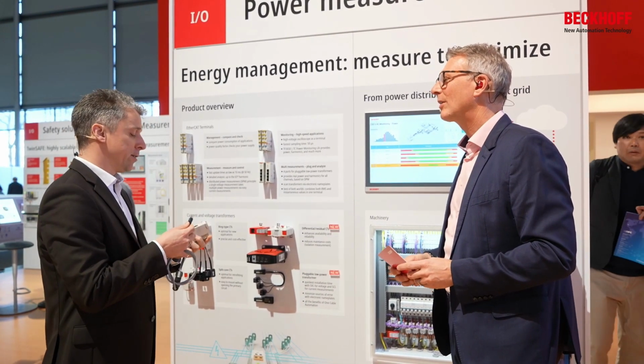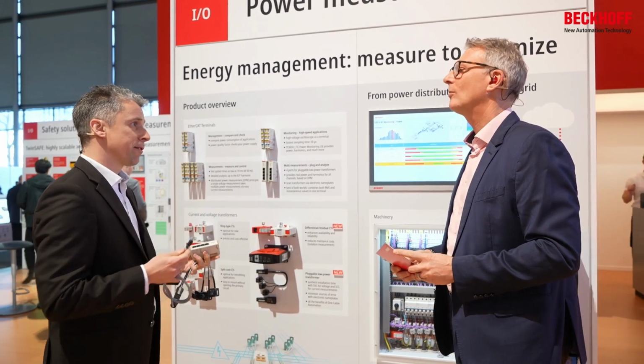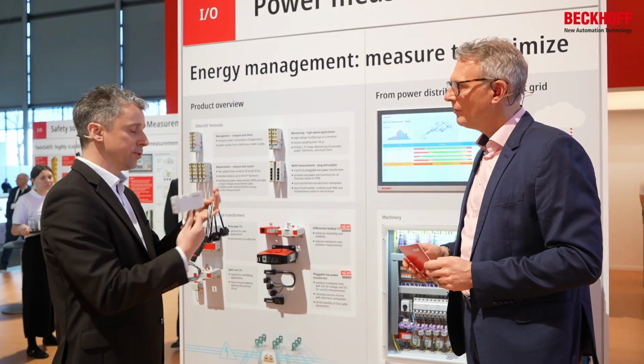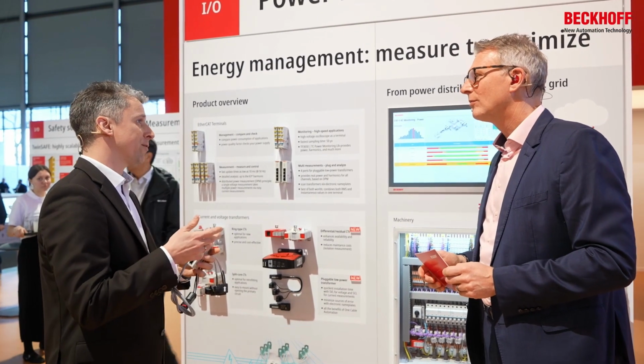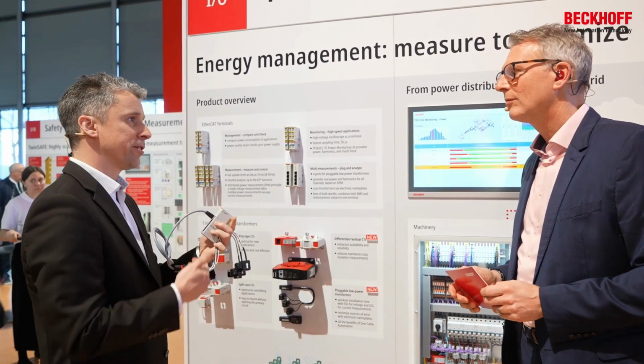Here we use 330 millivolt, 3 times, for 3 current transformers. And then we still have 2 more cores left. These 2 we use for the electronic nameplate. This is really handy, because as soon as the terminal is connected mechanically to the transformer, it can read out what kind of transformer is connected.